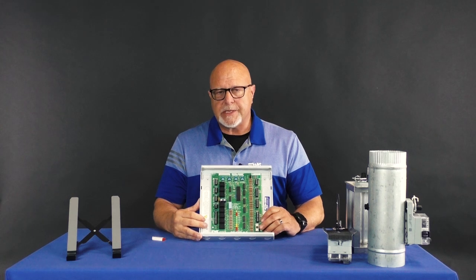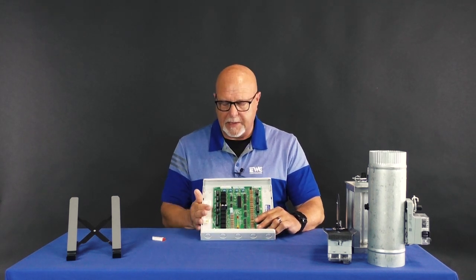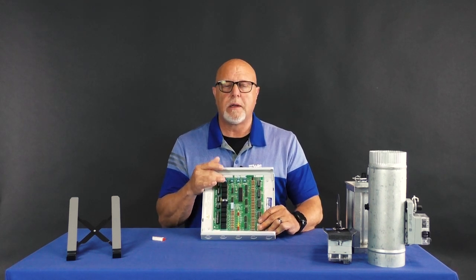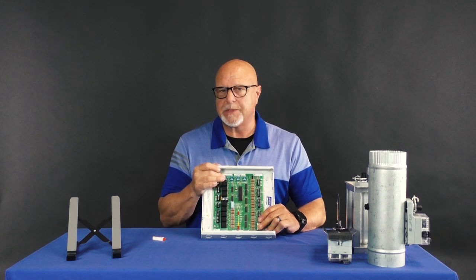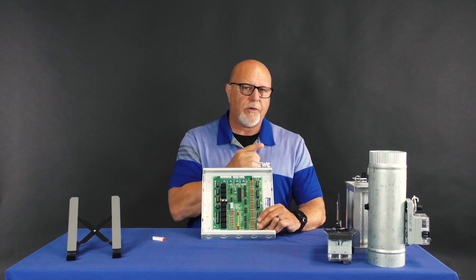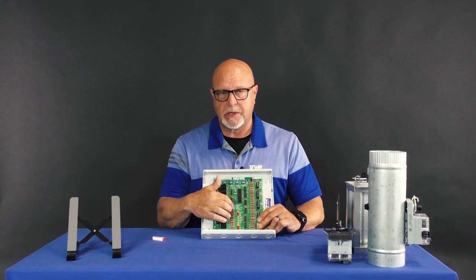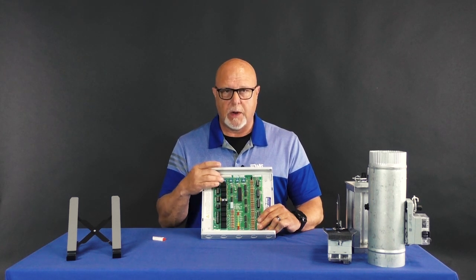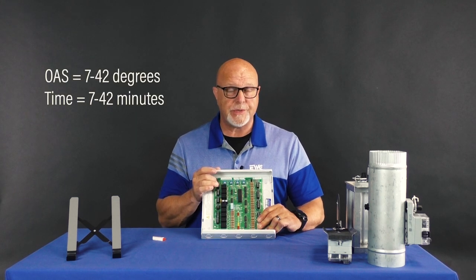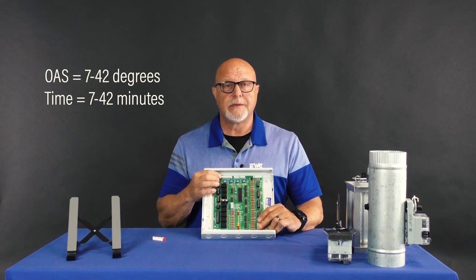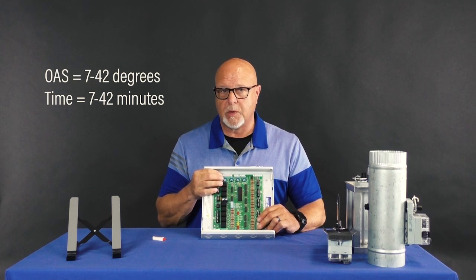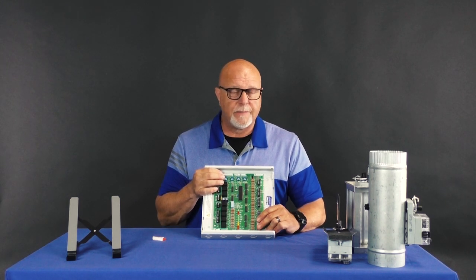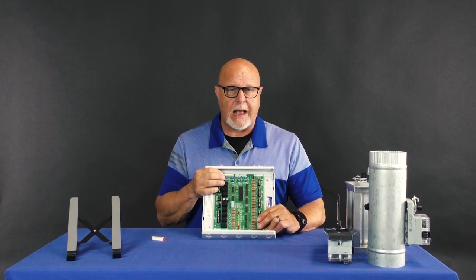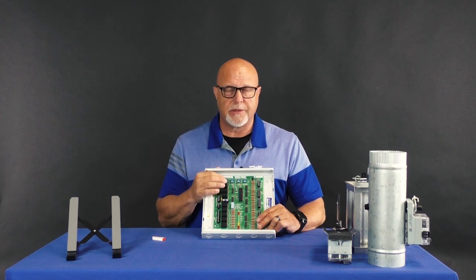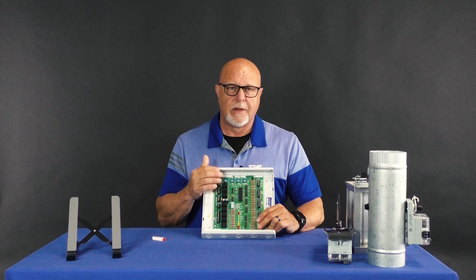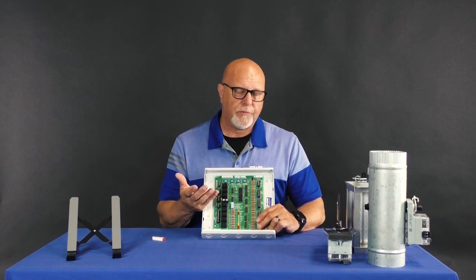As far as staging, like I said, it's 3 stages of heat, 2 stages of cooling, and in the dual fuel application, you actually set your outdoor balance point on this left-hand staging potentiometer. This left-hand staging potentiometer is either time or outdoor air temperature. By selecting time or outdoor air sensor on the dip switch, that determines what this is monitoring. If you set it to OAS, it's 7 to 42 degrees. If you set it to time, it is 7 to 42 minutes. Very unique feature in this board. With a very cheap, economical, standard heat-cool thermostat or heat pump stat, and an outdoor air sensor costing less than 30 bucks, I can operate a dual fuel situation without the need of a very expensive thermostat that has dual fuel built into it.